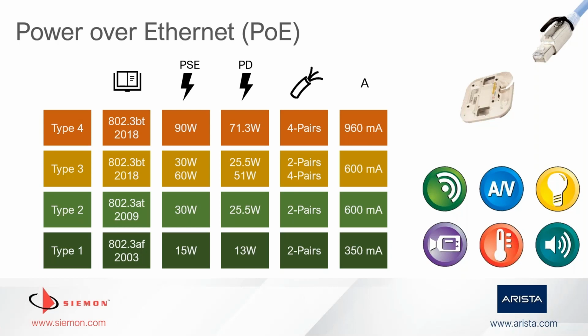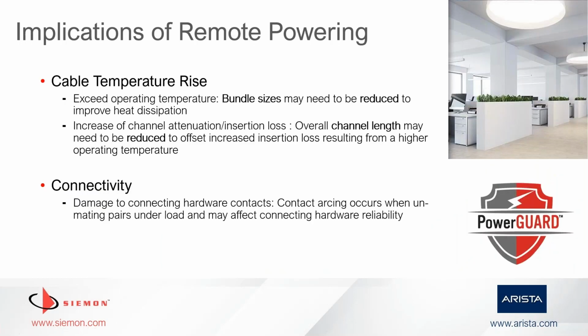We can see that the latest types of PoE are now expected to deliver higher levels of power, growing up to 60 and 90 watts, working typically on 4 pairs with a 15% loss for type 3 and almost 20% loss of power along the link for type 4. So along this new standard, we can see also some improvements in power effectiveness, but all of this has a direct impact on the cable specification that would be needed.